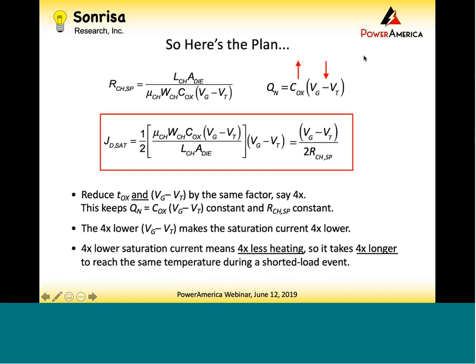So the 4 times lower saturation current is going to give me 4 times less heating. It's going to take 4 times longer to reach that required temperature. And therefore, I have 4 times longer short circuit withstand time.